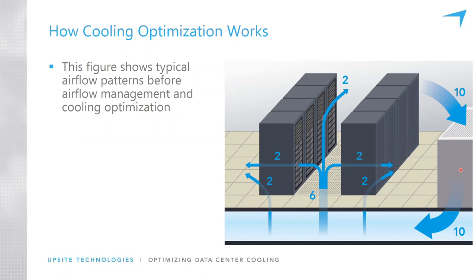Generally, the volumetric flow rate of air through cooling units and IT equipment in North America is considered in terms of CFM, cubic feet per minute. A cooling unit might have 10, 15, 20,000 CFM. But we're going to keep the numbers very simple and say that all the air moving through all the cooling units in the room is 10 units of air. So if 10 units of air go down into a cooling unit, 10 units come out.